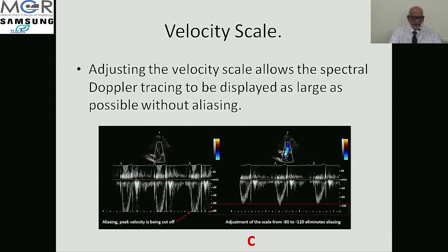Now velocity scale. Adjusting the velocity scale allows the spectral Doppler tracing to be displayed as large as possible without aliasing. Here on the left side you can see that the peak is cut off, it has aliased and is shown on the opposite side of the baseline. If you adjust the scale, the whole envelope can be seen properly. This is important for both CW and PW Doppler.